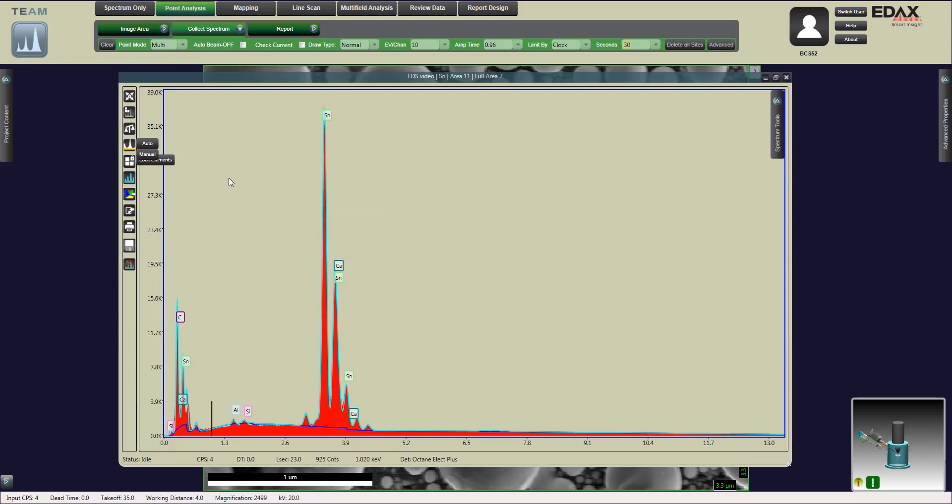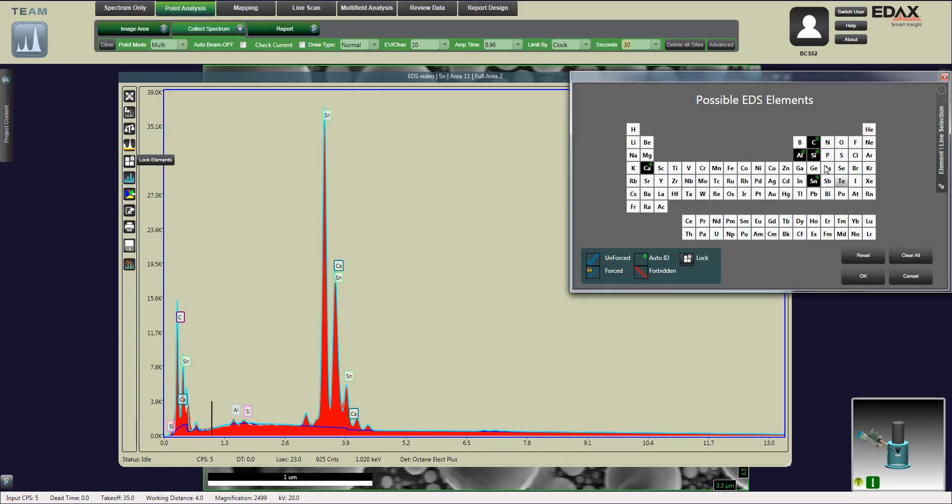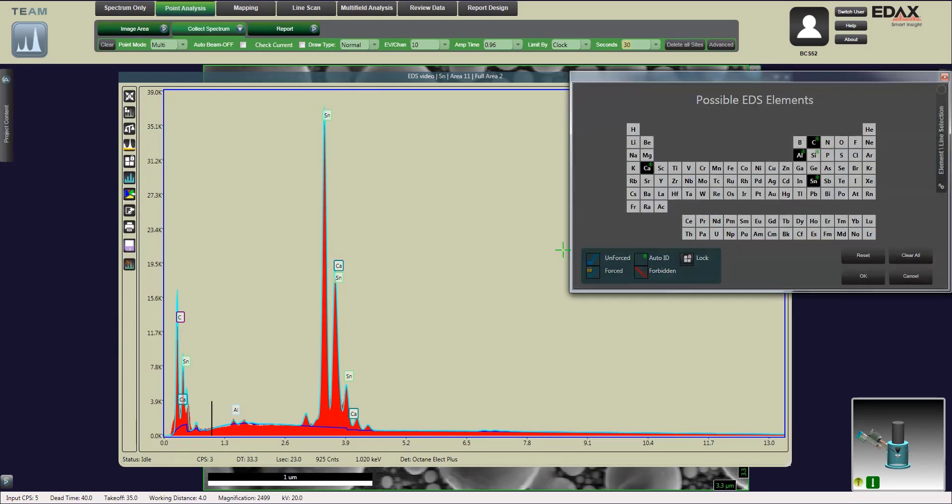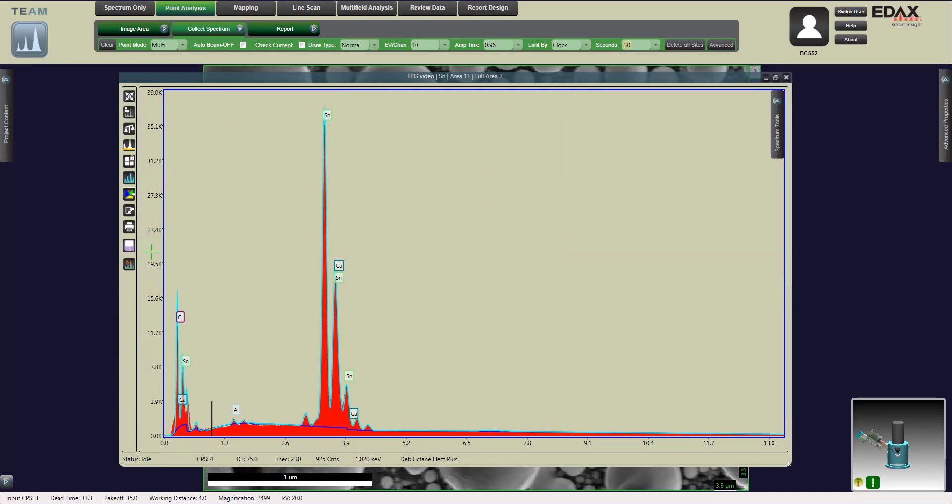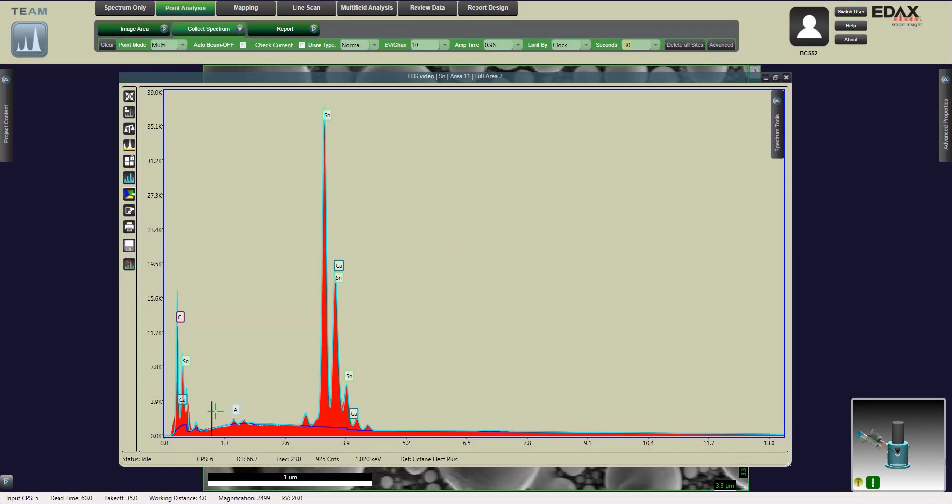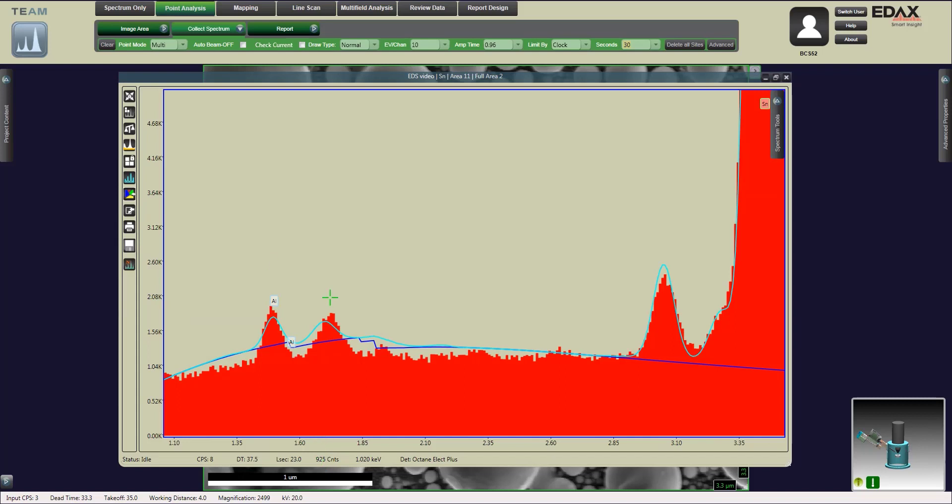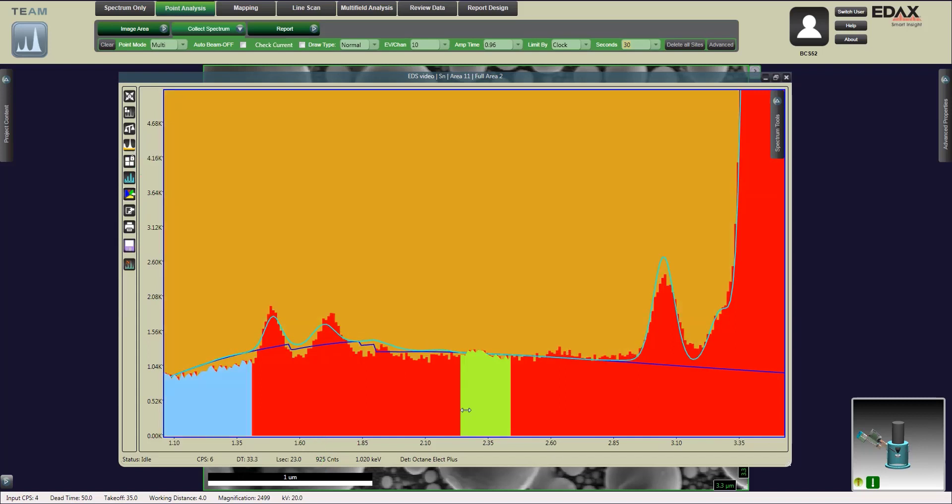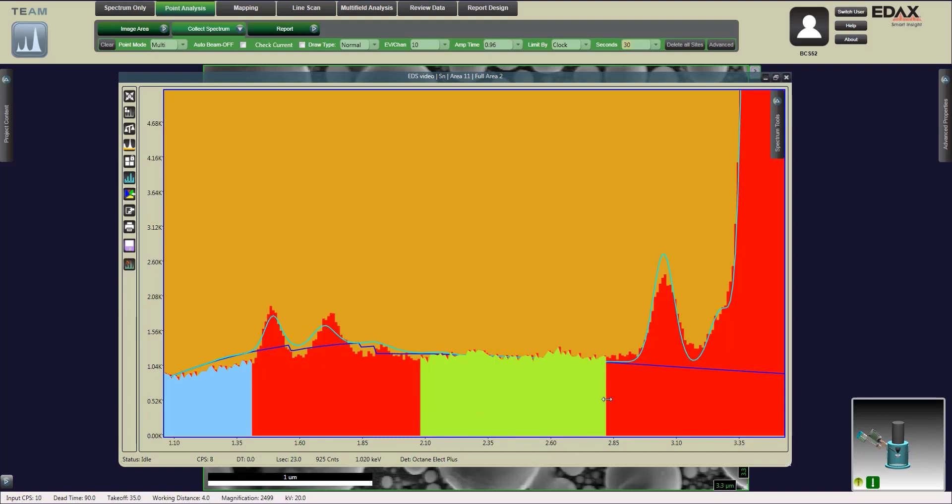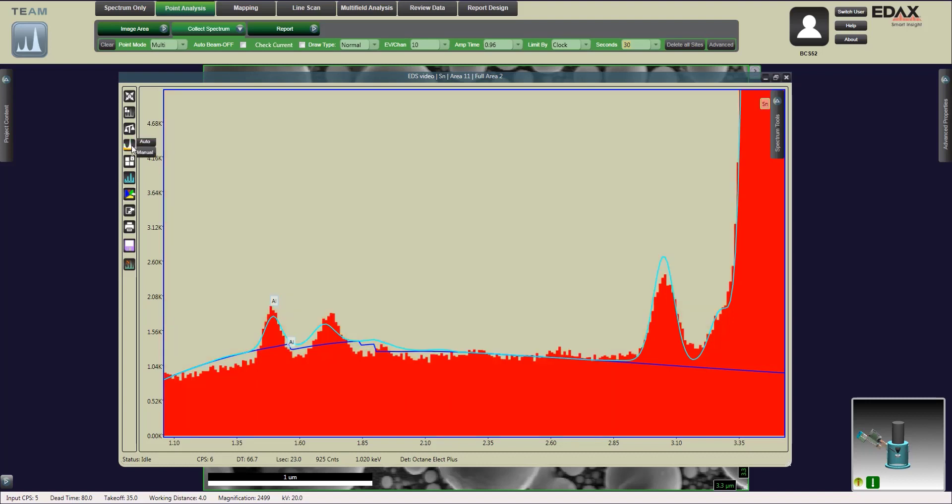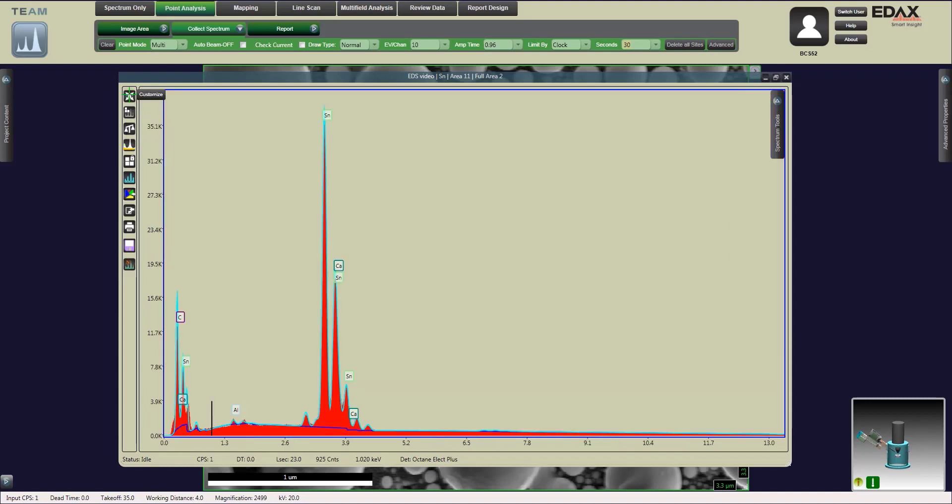If we believe this is not a silicon peak, we can always hit the table elements, unselect silicon, and then save the elements list once again. We still have a little bit of the background that's off, so I'm going to adjust that. Your background should follow the actual background that you have and shouldn't be above or below by too far on your data.